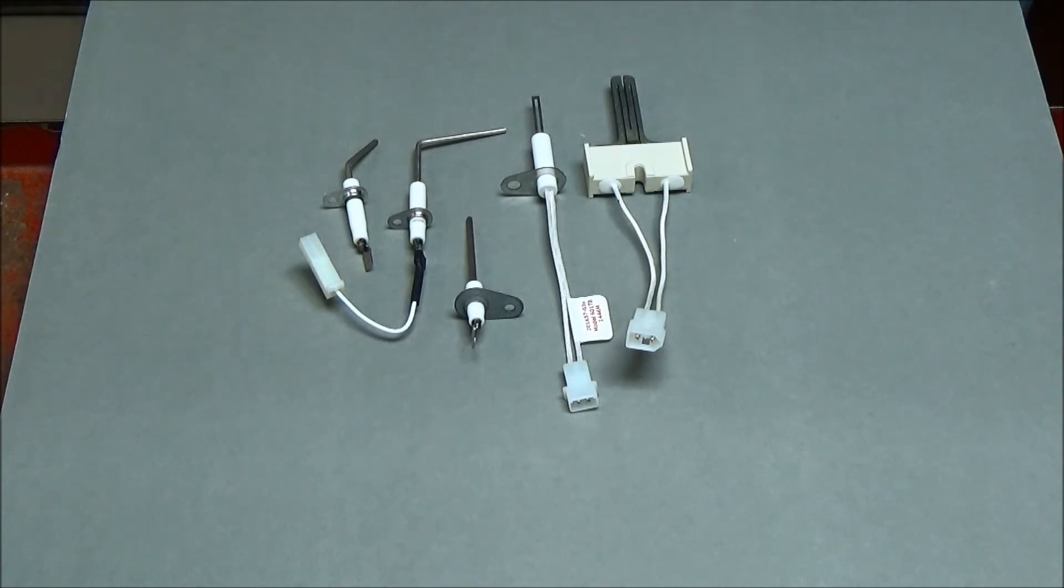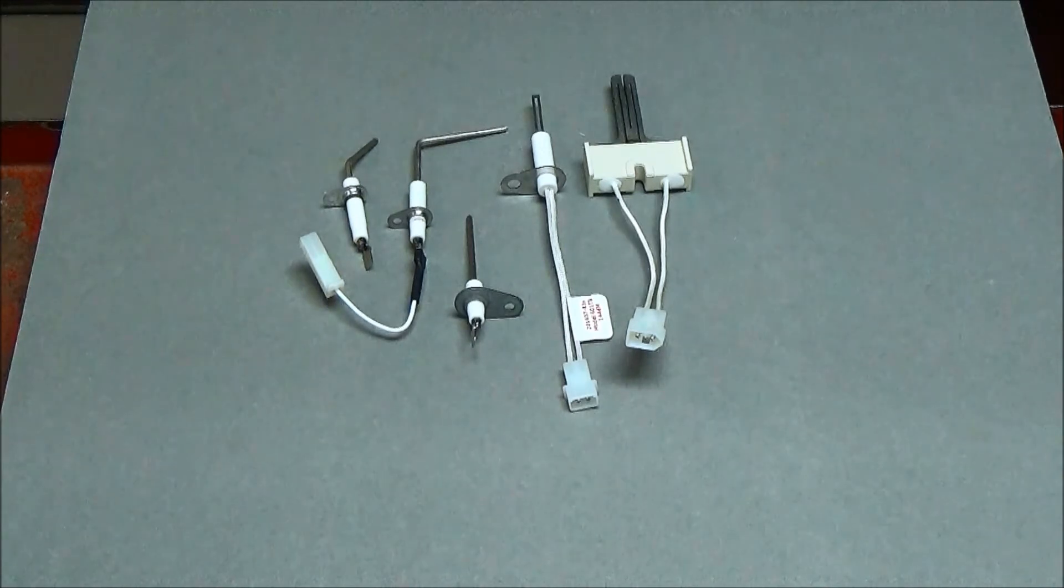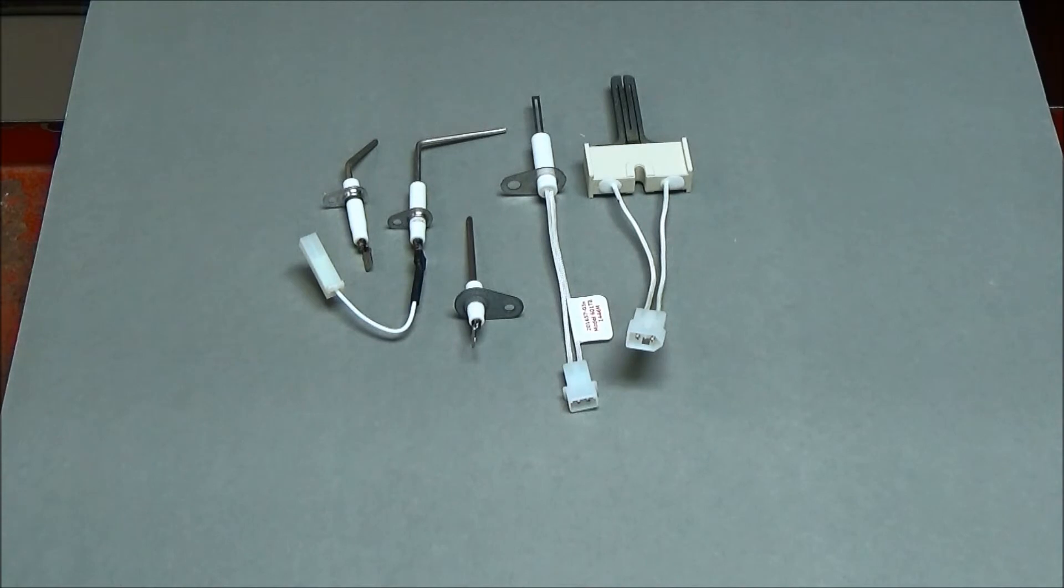On a call from the thermostat, the draft inducer will start. There's a draft inducer pressure switch that proves to the main circuit board that the draft inducer is running. This starts a cycle called a purge cycle.